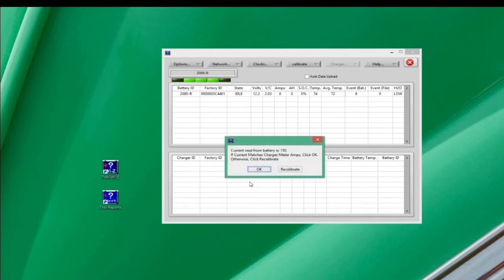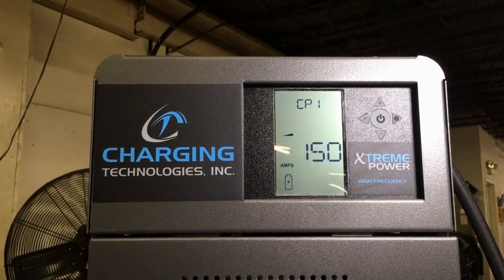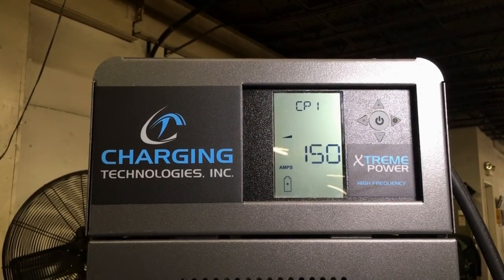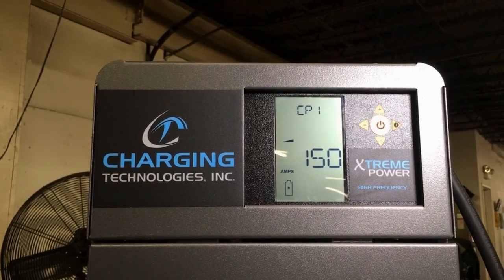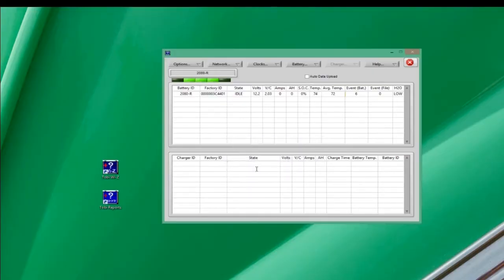It's putting that in the TOBi, and now it's going to read the current going through. It says it's reading 150. Look at the screen. I see that we're at 150, so we've got a dead on calibration. Okay. And that's the minimum. That's finished. That's what you have to do to set up the TOBi to the battery and to calibrate the shunt. That calibration should be within 3 amps for you to have a good calibration. If you don't get it within 3 amps, you should recalibrate.